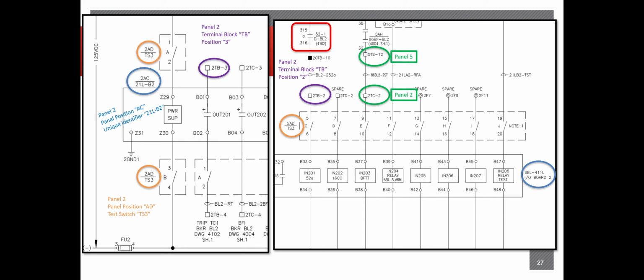That's what we call an anti-pump, which I can just glance over very briefly. An anti-pump scheme is a safety protocol for breaker failure situations. Pretty much what happens is, if the circuit isn't hooked up a certain way, the breaker could close in and then continuously keep trying to close in. The reason why that's an issue is the way the breaker closes is run by a motor. So if that motor keeps firing off, and these motors sometimes put out hundreds of amps at a time just to operate the breaker, just to close it. If that closing mechanism keeps occurring, it keeps popping out hundreds and hundreds of amps over and over again, that's going to heat up and eventually fail to the point where the breaker will just be a pile of junk and it won't work anymore.